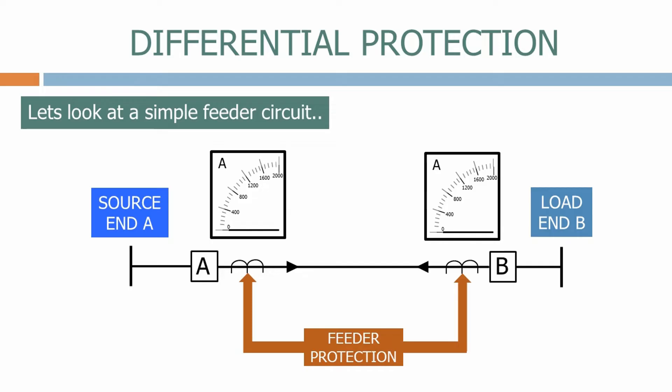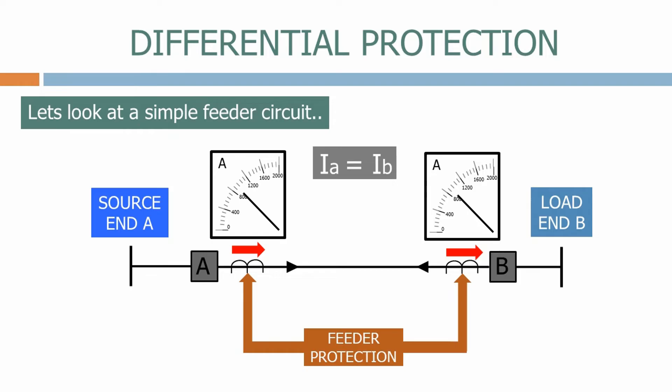Let's now close the circuit breakers. Current will now flow from the source through the current transformers at End A, along the feeder and through the current transformers at End B. The magnitude of the current will depend on the loads applied at End B. Regardless of the current magnitudes, if the system is healthy, the current flowing through End A will equal the current flowing through End B.